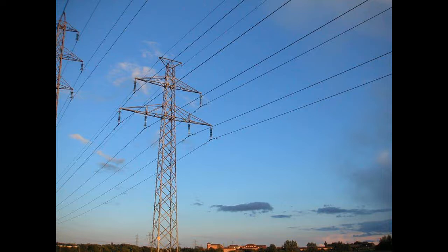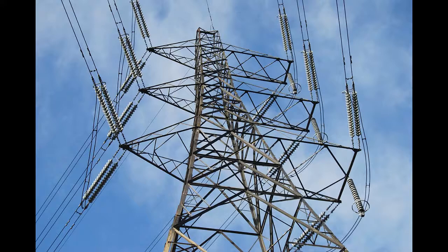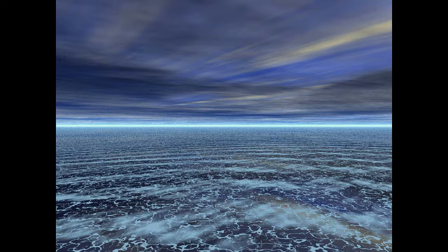That makes for an active device, one that looks at what current is flowing and makes decisions in real time. That's a lot more expensive than a passive device. In the United States alone, approximately 5,000 vulnerable transformers would have to be retrofitted at a cost of perhaps $100,000 each, plus installation. So it would make little sense to retrofit only a few transformers.